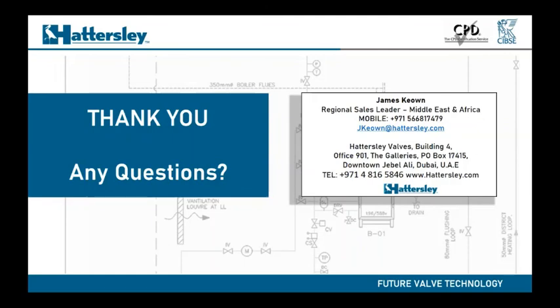The second reason is the PICV itself. Yes, you have got a percentage performance. So a manufacturer, shall I say, could set it to, say for instance, setting 3. But when it gets to site, you may need to just alter that a fraction. Again, it could be to do with repeatability. It could be to do with it being slightly moved in transit, vibrations, etc. Or it could be that you've got slight manufacturing tolerances. So again, you may need to just fractionally move it. So I would always say, yes, there is that possibility.